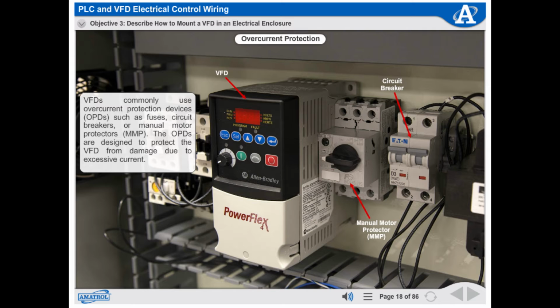VFDs commonly use overcurrent protection devices such as fuses, circuit breakers, or manual motor protectors. The OPDs are designed to protect the VFD from damage due to excessive current. The graphic shows an MMP mounted on the DIN rail between the main power disconnect switch and VFD.